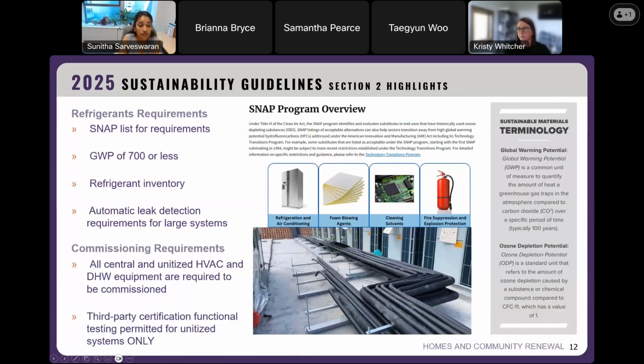To go into more detail on the section 2 updates, as I mentioned, there is a new subsection for refrigerants. This subsection is focused on making sure projects are in compliance with the EPA's phase down for refrigerants. We are now directly referencing the SNAP list for acceptable refrigerants, linked directly in our guidelines. We're also requiring that projects use refrigerants with a global warming potential of 700 or less.